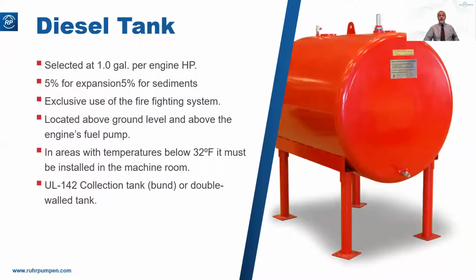The diesel tank: you need 1 diesel tank for each pump. You can't have a common diesel tank. It's sized 1 gallon per engine horsepower. That will nominally give you an 8-hour capacity. And it shall be located above ground level and above the engine's fuel pump.